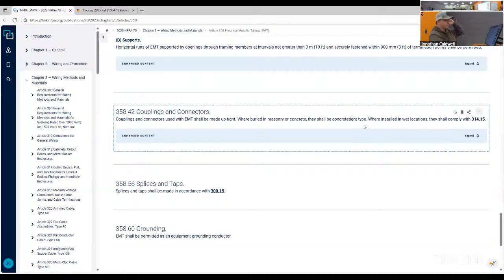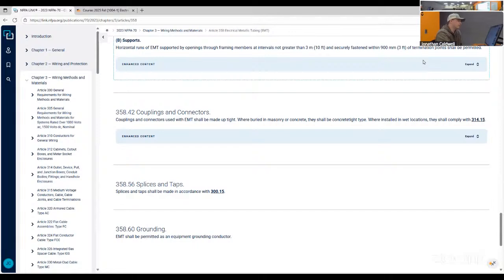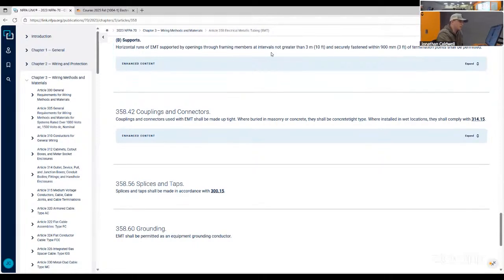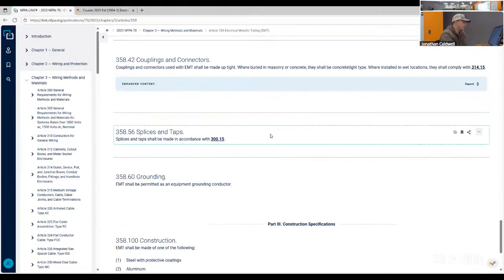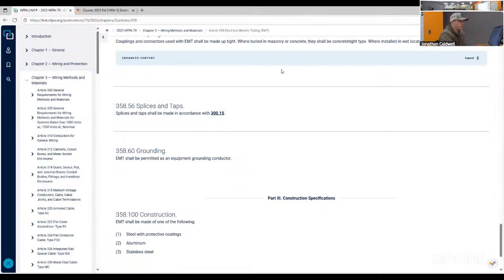Couplings and connectors used with EMT shall be made up tight. Where buried in masonry or concrete, they shall be concrete tight. Where installed in wet locations, they shall comply with 314.15. Something to note, set screw fittings can technically be concrete tight. All you have to do is tape them. That's actually a manufacturer recommended install. But make sure you're using those correct manufactured type fittings. Another thing to note with the connection into the box, the connector into the conduit needs to be nice and flush and all that. I know sometimes with EMT, we kind of, it is what it is. Let me just stick it in there, call it a day, but.